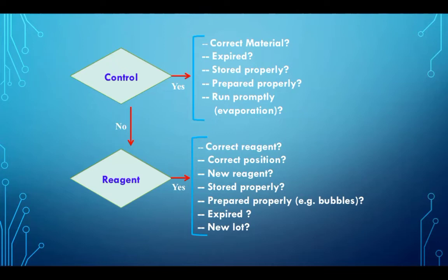An additional thing, sometimes what may happen when you are running control, you are preparing suppose 10 aliquots. For 4-5 aliquots, you are getting appropriate results. Then you start getting some trend. The results are lower than expected and they are moving in one direction.